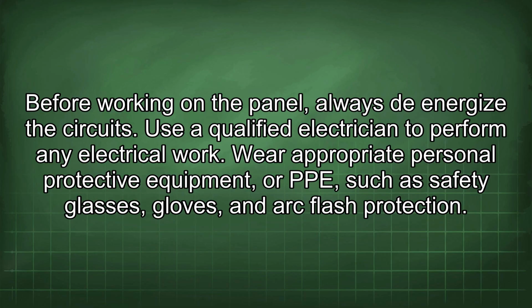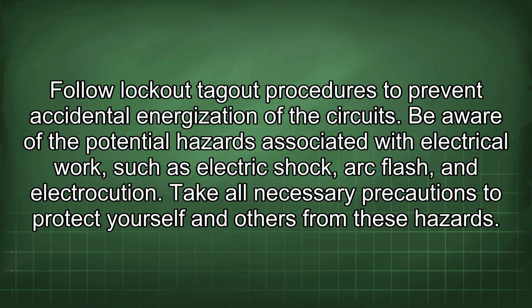Before working on the panel, always de-energize the circuits. Use a qualified electrician to perform any electrical work. Wear appropriate personal protective equipment, or PPE, such as safety glasses, gloves, and arc flash protection. Follow lockout tagout procedures to prevent accidental energization of the circuits. Be aware of the potential hazards associated with electrical work, such as electric shock, arc flash, and electrocution. Take all necessary precautions to protect yourself and others from these hazards.